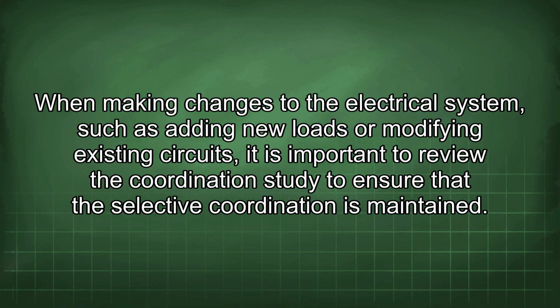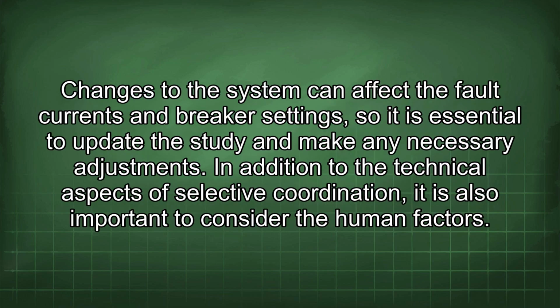When making changes to the electrical system, such as adding new loads or modifying existing circuits, it is important to review the coordination study to ensure that the selective coordination is maintained. Changes to the system can affect the fault currents and breaker settings, so it is essential to update the study and make any necessary adjustments.